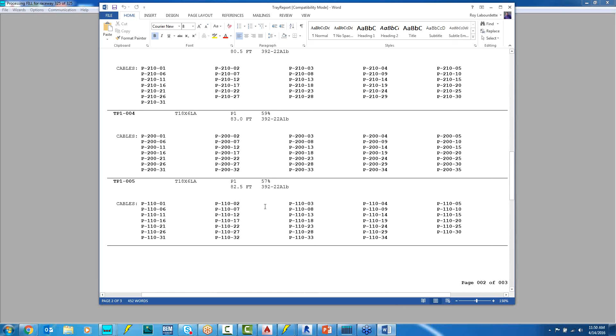Similarly, we could do the same thing with conduit, and if I do a DB query, I can find my conduits that are, let's just pick everything that has an RP, and get that report. And again, I want a list of the cables that are contained in a conduit. I can give it a name. Do I want to resize these conduits? Yes, I'm going to let the program resize the conduit based on the fill percentage and the constraints that I've set. Now on my project, I set the minimum EMT size at 1 inch.